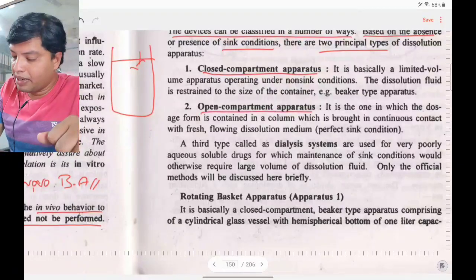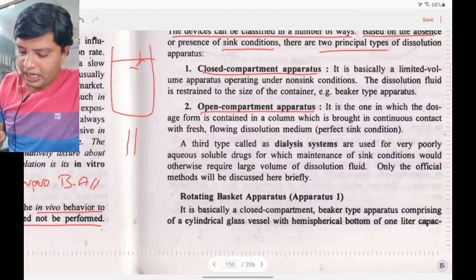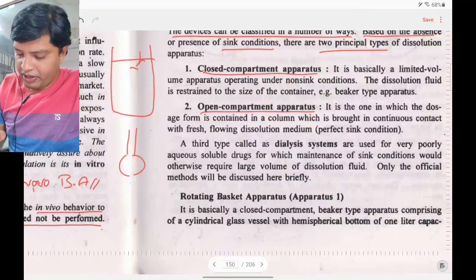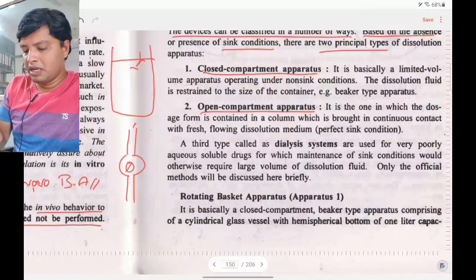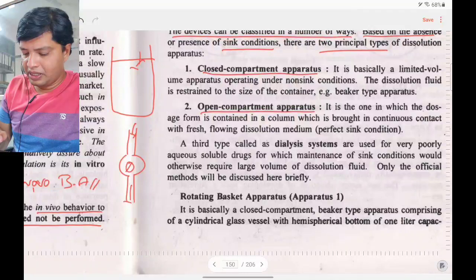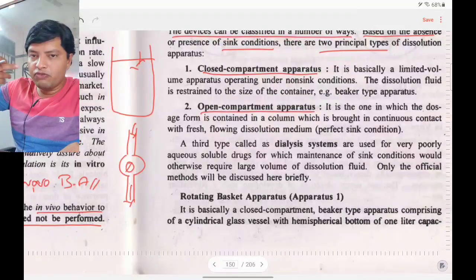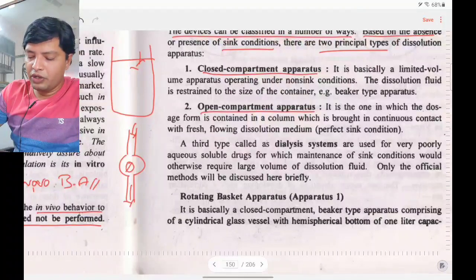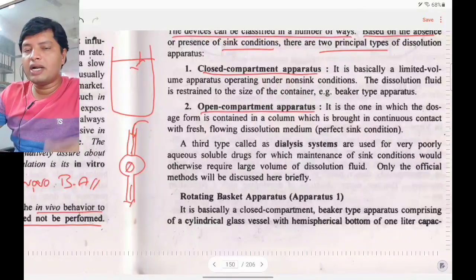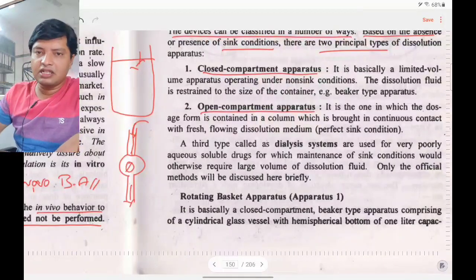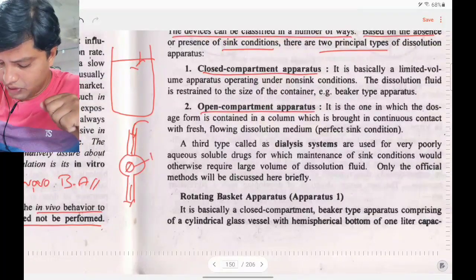The second type is the open compartment apparatus: there is a cell in which the dosage form is placed, and dissolution fluid flows continuously so that fresh medium is always in contact with the dosage form, maintaining sink condition. This is called the flow-through cell.